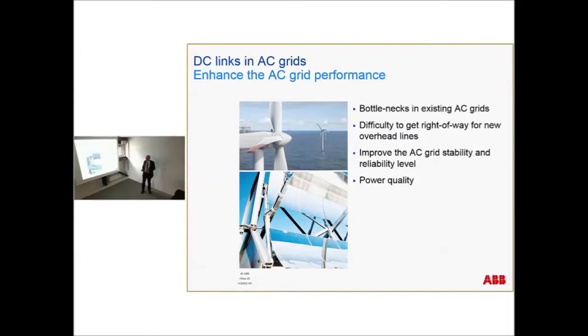And this is an HVDC Light application mainly. By installing HVDC links in parallel with the existing AC links, not only do you increase the power in the new DC link, you can also increase the power transmission in the existing AC link, since you improve the AC grid stability and the reliability level. You can avoid bottlenecks here, and you can convert lines to DC lines, increasing the power transmission capability by a factor of 2 or 3, thereby avoiding discussions on new rights of way.